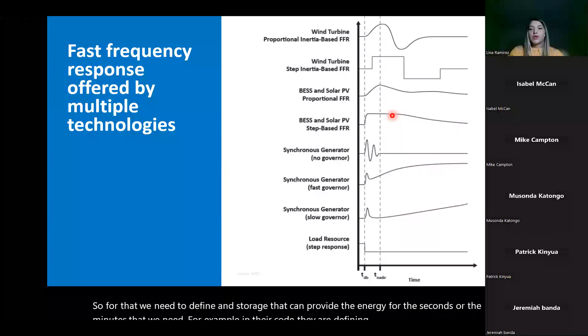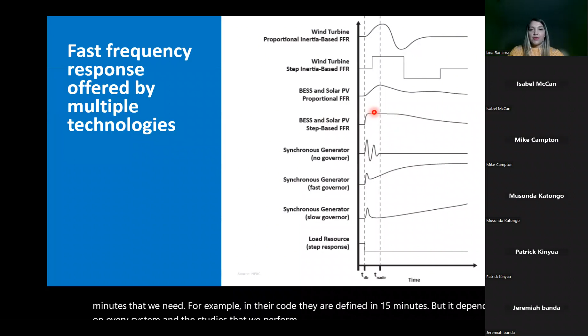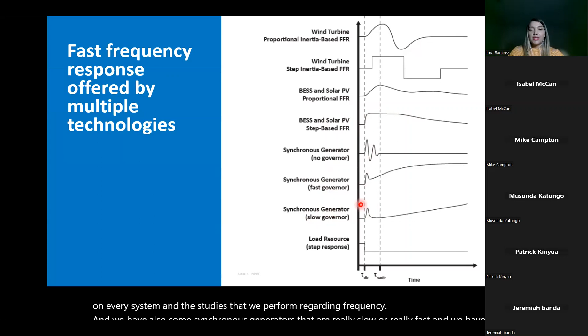For that, we need to define a storage that can provide the energy for the seconds or the minutes that we need. For example, in ERCOT they are defining 15 minutes, but it depends on every system and the studies that we perform regarding frequency. We also have some synchronous generators that are really slow or really fast, and we have different responses. Load response for frequency is really good. It is also in seconds, they can maintain that response, and it can be a market product, as it is in ERCOT.